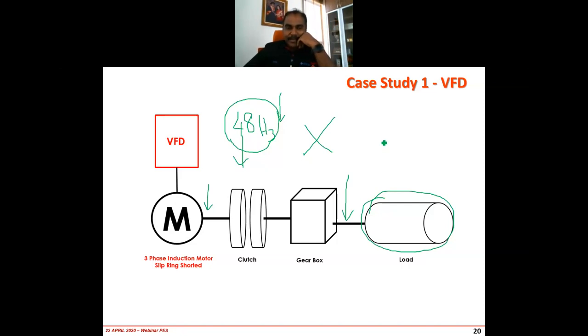There's no saving at all, because eventually, after about 1 month, the company complained and they brought this back to 50 hertz. That means now this particular system is running with a VFD at 50 hertz as normal. That means you have to maintain the VFD. You have to pay additional cost for the air conditioning system. You have to maintain this VFD, which is additional maintenance cost, with zero savings. Okay, this is a bad example of where you should not be using the VFD. So that means not all motor systems should be connected to the VFD.